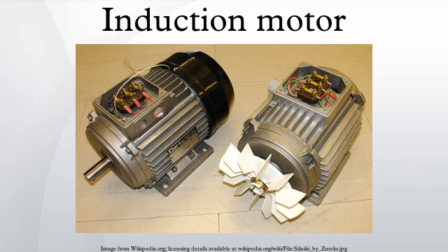Larger single-phase motors have a second stator winding fed with out-of-phase current. Such currents may be created by feeding the winding through a capacitor or having it receive different values of inductance and resistance from the main winding. In capacitor start designs, the second winding is disconnected once the motor is up to speed, usually either by a centrifugal switch acting on weights on the motor shaft or a thermistor which heats up and increases its resistance, reducing the current through the second winding to an insignificant level. The capacitor run designs keep the second winding on when running, improving torque.